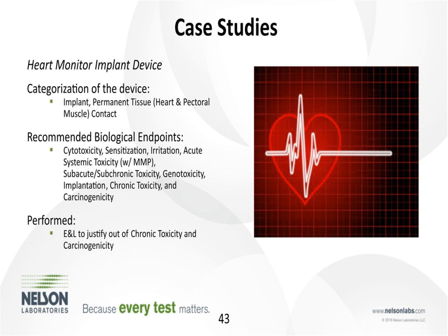Now, if you just can't get enough of case studies and you would like more examples, the new FDA guidance for industry that was just published in June 2016 is really great. It's on the use of ISO 10993-1, the biological evaluation of medical devices. They have many really great examples of both how material characterization and extractable leachable testing can be used in lieu of biocompatibility testing endpoints. And these are really examples that are embedded all throughout that document. I strongly encourage you to read that.